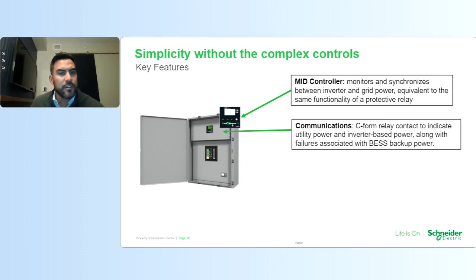The communication, as I mentioned, we use a C-form relay contact to indicate utility power and inverter-based power, along with failures associated with battery energy storage backup power. So it's a normally energized relay. We send a contact signal to the energy management system or the inverters in that battery energy storage system to signal when utility is present, when utility is lost, when our device is isolated, to allow that energy storage system to come online and safely provide emergency power.